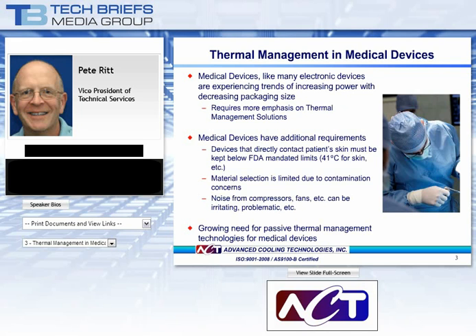Medical devices, like many electronic devices, are experiencing trends of increasing power with decreasing packaging size. They are smaller, more functional, and more powerful. And this requires greater emphasis on thermal management solutions. But medical devices have additional requirements. They also have the human element to consider. For example, devices that directly contact the skin must be kept below FDA-mandated limits of 41 degrees C. Also, material selection is limited due to contamination concerns. Copper, for example, can't be used in some devices for this reason.